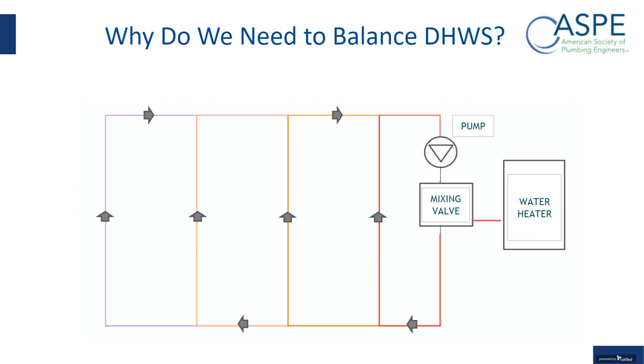So what you do then is put balancing valves, in this case at the top of each one of these risers. The idea is to normalize all of these risers so that they're all getting the flow they need in their particular branches to overcome the heat loss. For this type of basic design, once you put balancing valves up there, they could be any type of balancing valves: manual balancing valves, pressure independent, thermostatic, or electric.